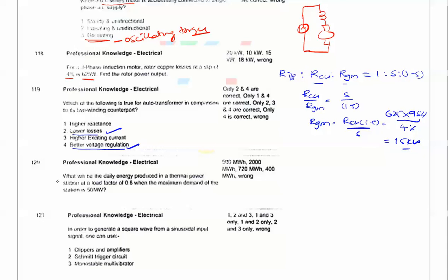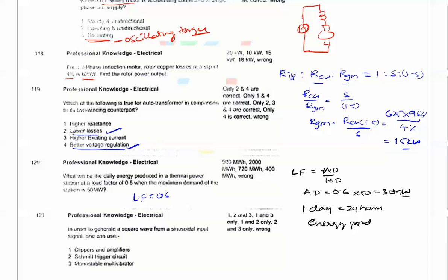And the next question here is, what will be the daily energy produced in a thermal power plant at a load factor of 0.6 when the maximum demand on the station is 50 megawatts? We know the formula for load factor: load factor is equal to average demand by maximum demand. So average demand is equal to 0.6 into 50, which is nothing but 30 megawatts of power generated. Now daily means for one day, 24 hours. So if you multiply this with 24, you will get the energy produced per day. So the energy produced is 30 into 24 hours, and you will get 720 megawatt hours as the answer.